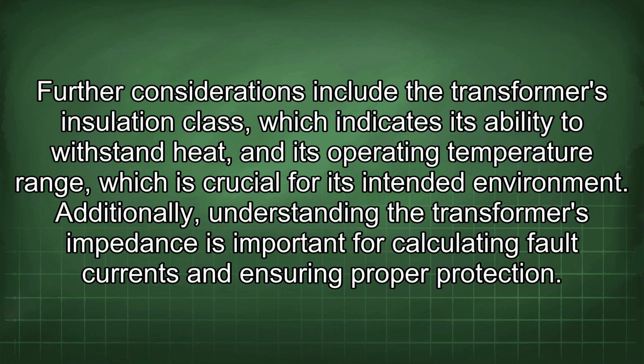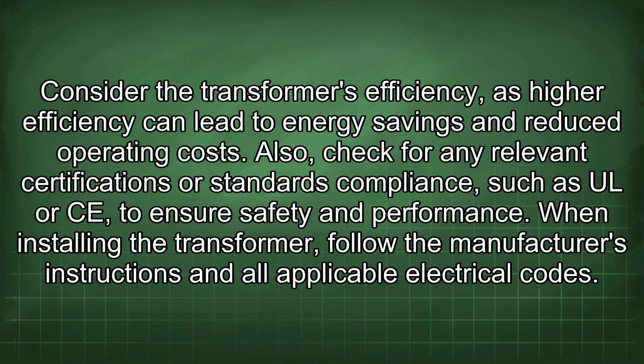Further considerations include the transformer's insulation class, which indicates its ability to withstand heat, and its operating temperature range, which is crucial for its intended environment. Additionally, understanding the transformer's impedance is important for calculating fault currents and ensuring proper protection. Consider the transformer's efficiency, as higher efficiency can lead to energy savings and reduced operating costs. Also, check for any relevant certifications or standards compliance, such as UL or CE, to ensure safety and performance.